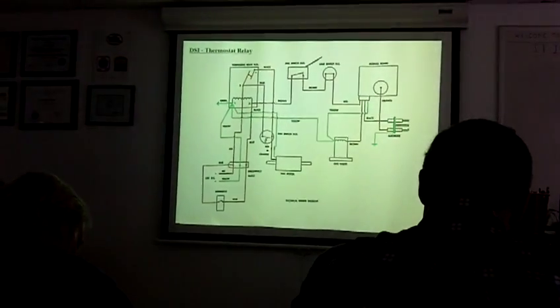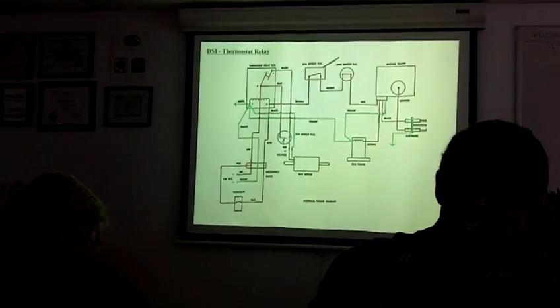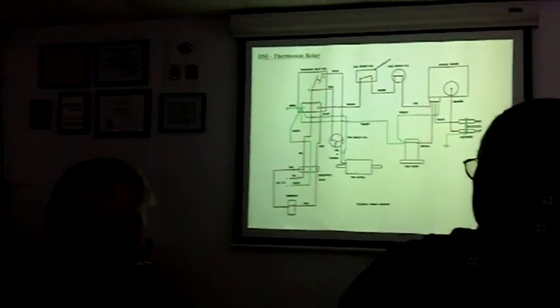And your connection's there, your connections over here to the chassis have to be good. So those are all things you want to check if you think you're getting a sense problem, or you might be suffering from a sense problem on the furnace.